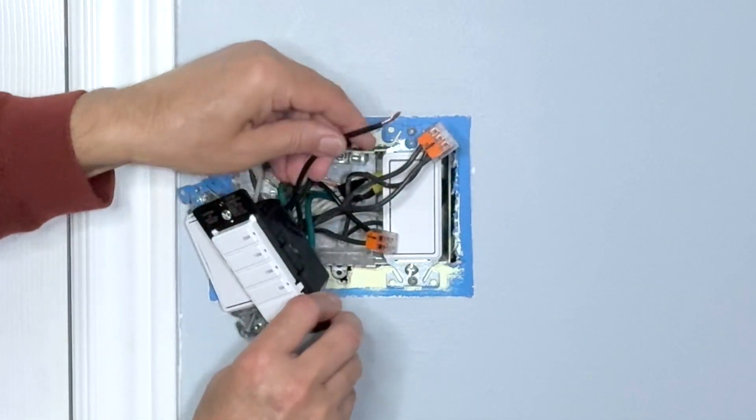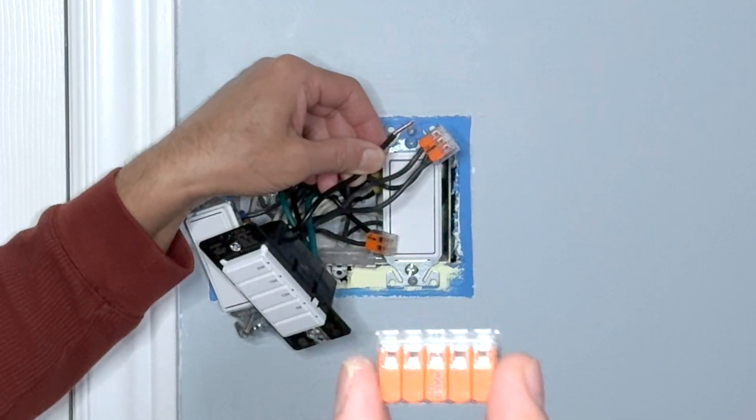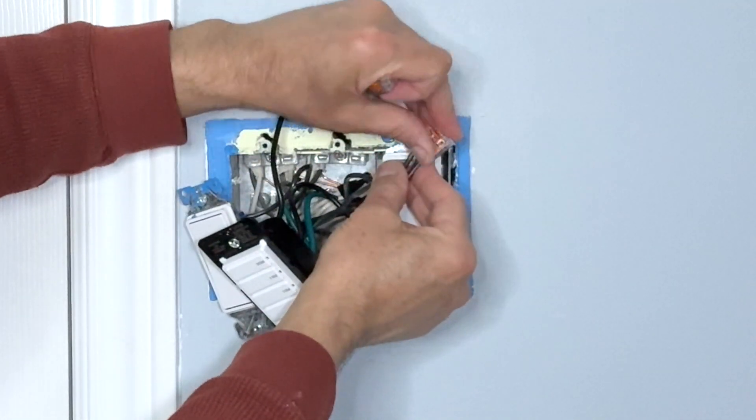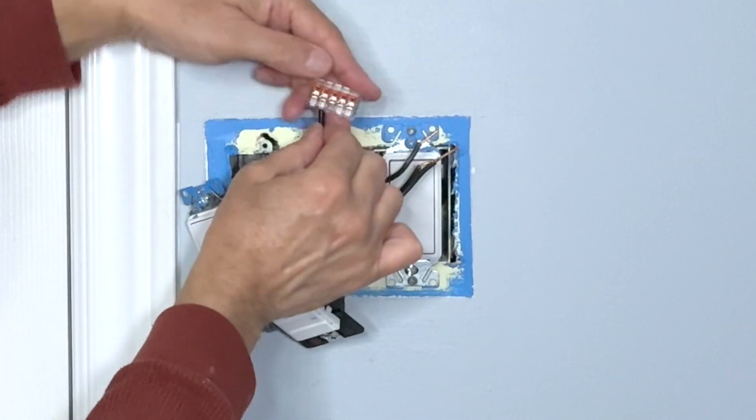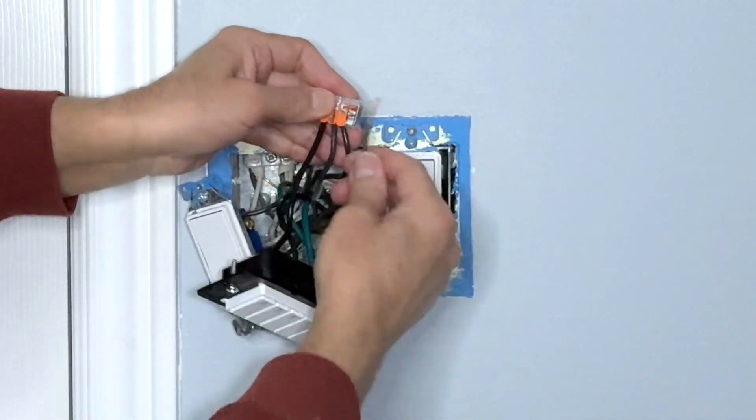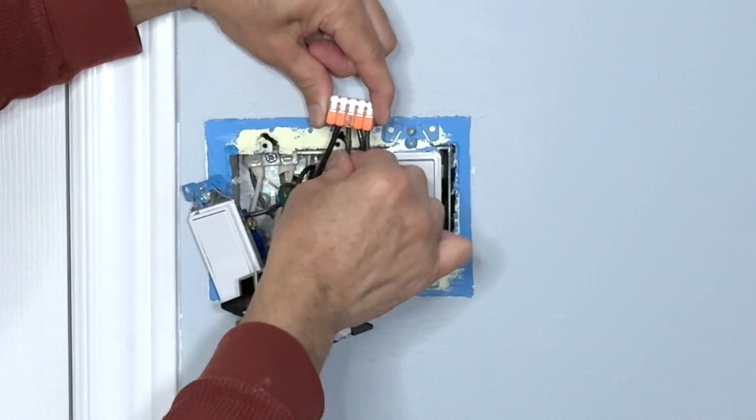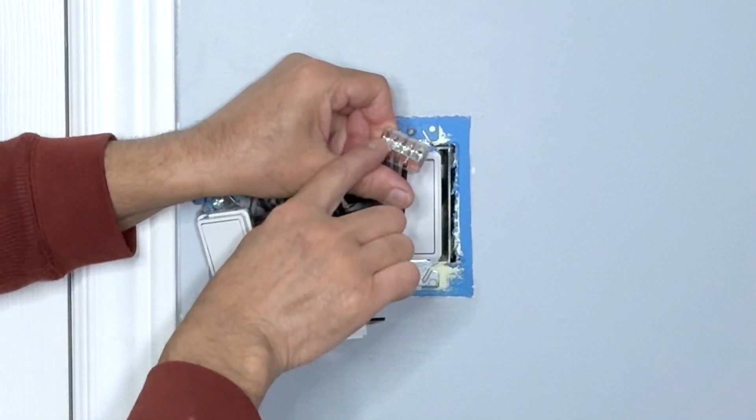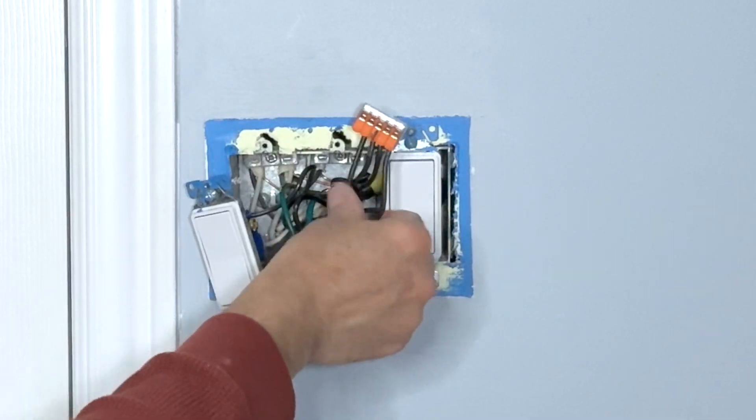Next my line wire. Now I have to connect four black wires together. For this I will use a 5 pin WAGO lever nut connector. Remove this temporary connector. Free all these wires. And then insert all these wires into the WAGO lever nut connector. Pull each of the wires a bit to make sure the connection is not loose. Also on the back side you can see the bare copper must go all the way up to the top. Push these wires into the box and then tighten these.